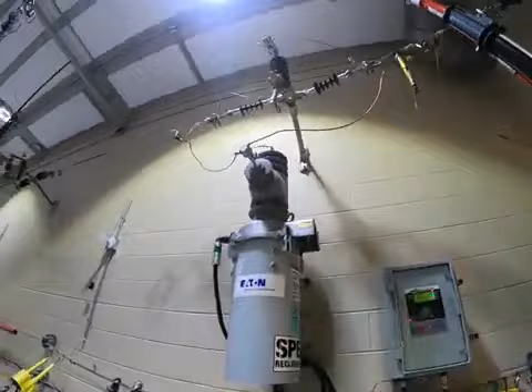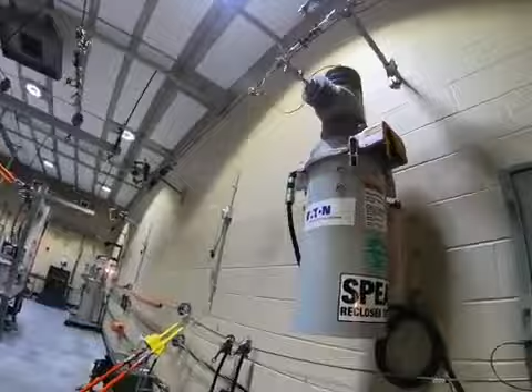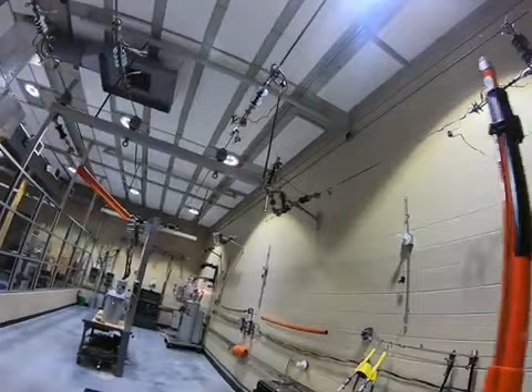So the first step to make sure you keep the lights on to the customer when changing out an OCR, or in this case a vacuum recloser. This is a single phase spear recloser, just a brand. It shows that its contacts are closed right now. Everybody's obviously hot. We got hot coming from here, up feed through there, stepping it down to that light down there. That light should stay on the whole time.